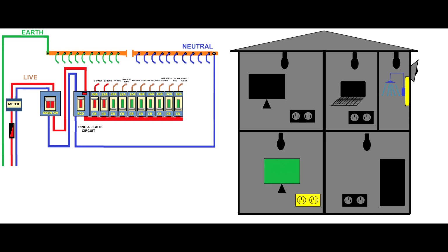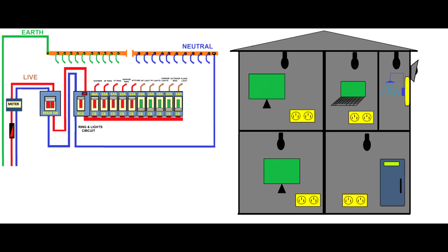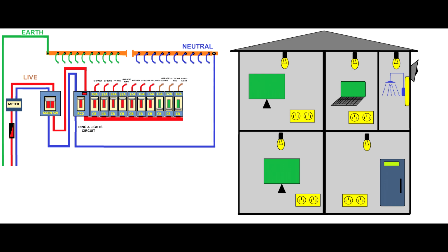Now the ground floor's ring circuit has been enabled. Now the first floor ring circuit has been enabled. So you have to turn them on one by one until the RCD trips. When you find the faulty circuit and you enable the circuit breaker, instantly the RCD will trip, or in a couple of minutes if it's some humidity problem, but that's a little bit more complicated. So look, slowly I'm reinstating the entire home.